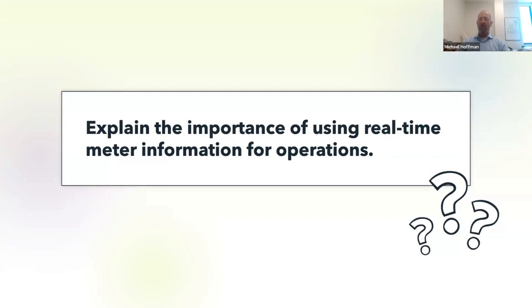For us at the university, we're on a large scale rate with the utility, which includes demand charges and a ratchet. For those not familiar, a typical demand charge is a cost per unit, usually cost per kilowatt at your peak demand over the billing period - whatever 15-minute interval you demanded the largest amount of power becomes your demand charge. With a ratchet like we have, they compare your billing period's worst peak to, in our case, 75% of our worst peak trailing the last year.